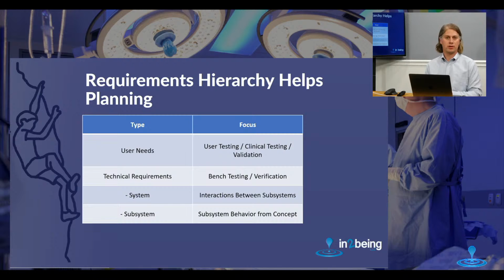There are different types of requirements that FDA does call out. At very least, there are user needs and technical requirements. In fact, there can be many more than that when you think about the types of risk analysis that happens under standards and mitigations that pop out of that process. There's many other aspects relating to usability, yet slightly nuanced and different from user needs and technical requirements.